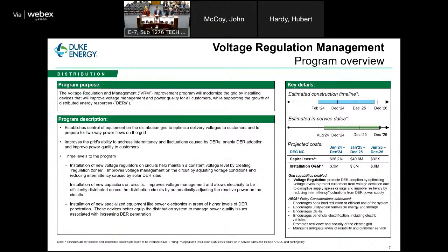There are really three levels of voltage regulation management equipment that will be deployed if needed. Voltage regulators and upgraded controls will be first. We may add capacitors to provide reactive power support if needed. And lastly, for circuits with high penetration of distributed energy resources, power electronics can be deployed to provide both voltage and reactive power support in areas of particularly high DER penetration.